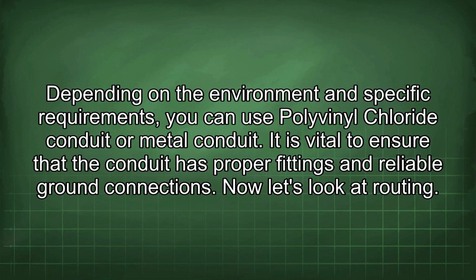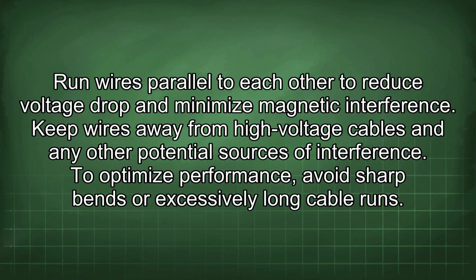Now let's look at routing. Run wires parallel to each other to reduce voltage drop and minimize magnetic interference. Keep wires away from high voltage cables and any other potential sources of interference. To optimize performance, avoid sharp bends or excessively long cable runs.